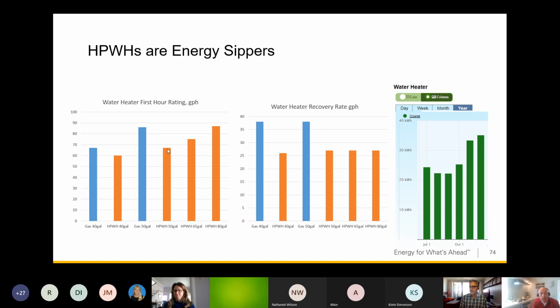And so to get back up to that same amount of first hour available hot water, you need an 80-gallon heat pump water heater, which is the bar on the right. That's because the recovery rate of heat pump water heaters is lower than the recovery rate of gas tank water heaters. So what this means is if you're used to a 50-gallon gas water heater for a typical size building, you might need an 80-gallon heat pump water heater or a 65-gallon heat pump water heater. It's a good rule of thumb to upsize the tank a little.